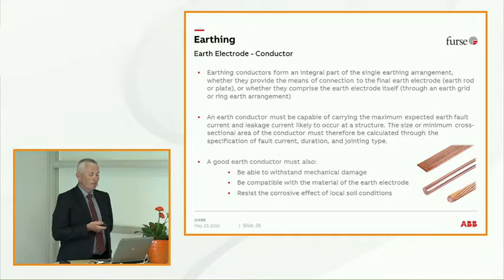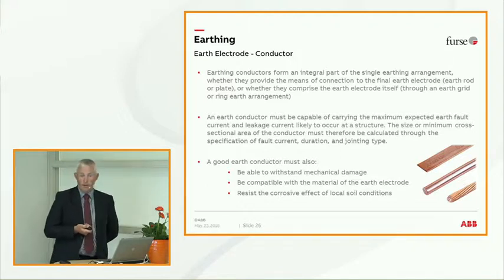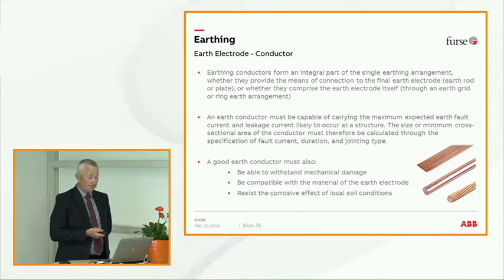The earth conductor must be capable of carrying the maximum expected earth fault current and leakage current. This is determined at earthing design, and when we do the earthing design, like I say, we look at the standards we're working to and we take effects like the soil resistivity into account. This can give us what we need to do current carrying capacity wise.